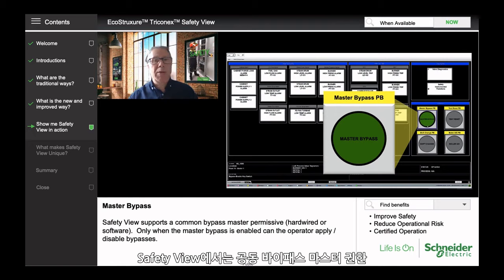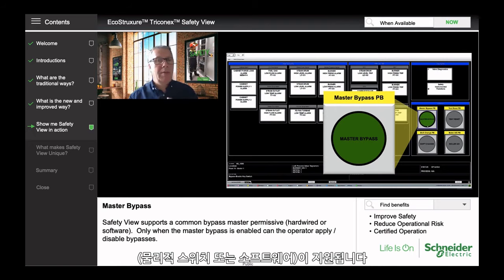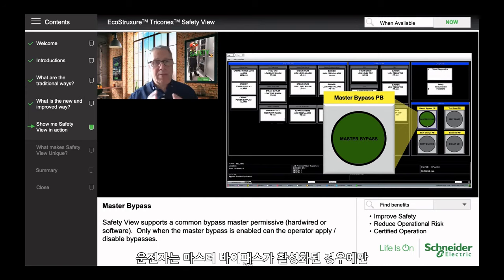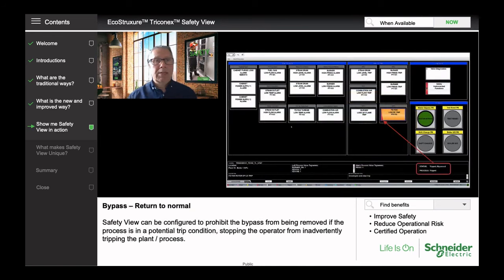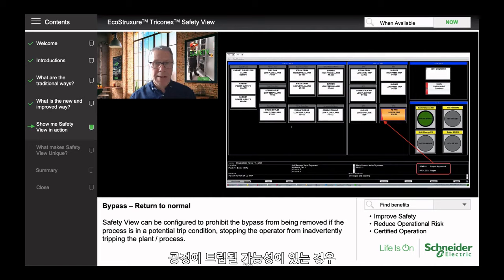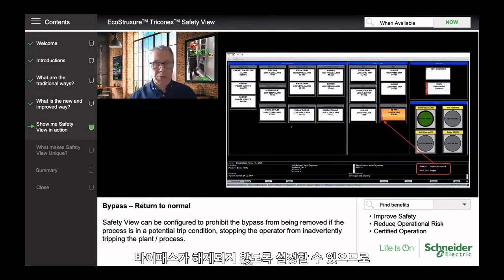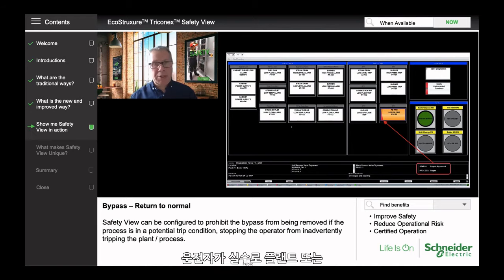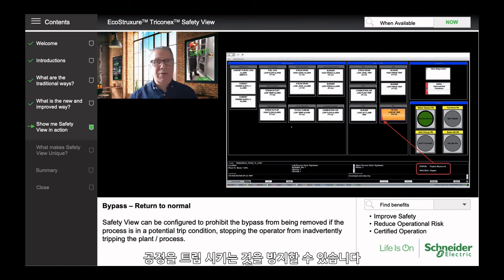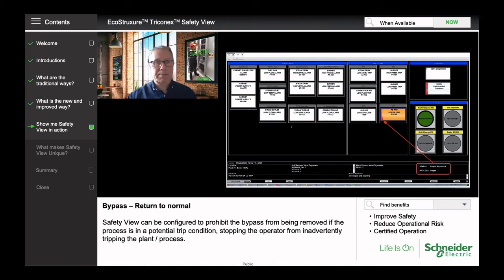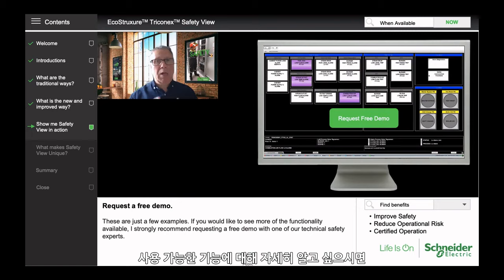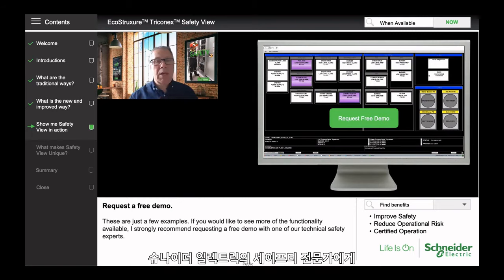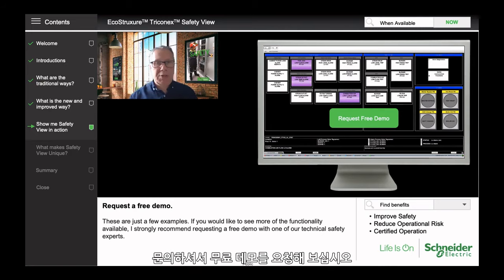SafetyView supports a common bypass master permissive, whether hardwired or software. Only when the master bypass is enabled can the operator then apply or disable bypasses. SafetyView can also be configured to prohibit a bypass from being removed if the process is in a potential trip condition, stopping the operator from inadvertently tripping the plant or the process. These are just a few examples of SafetyView functionality. If you'd like to see more, I strongly recommend requesting a free demo with one of our safety experts.